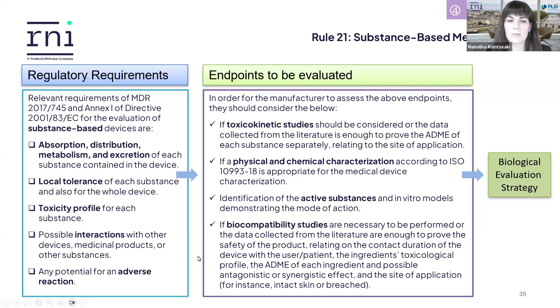We should perform a chemical characterization of the medical device in order to find any unidentified substance or any extractable and leachable substance coming from the whole manufacturing process or from the package or label. So we should be aware of any potential risk from those unidentified substances. In addition, we should make clear what the active substances in the medical device are and what biocompatibility studies are necessary to be performed in order to collect more data on safety.